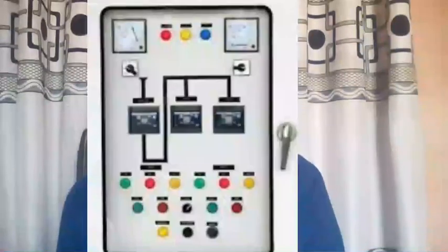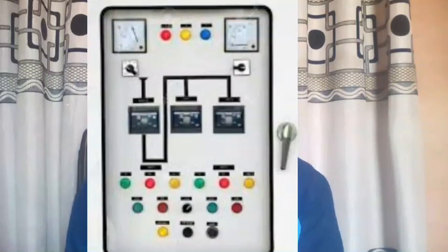And what is it used for? It's used to supply the remote control circuits. We open our breakers remotely, we close them remotely, and it uses the 110 volt. And some relays too use 110-volt supplies for their operation. Likewise, the annunciator alarms in our stations, some of them use the 110-volt battery, 110 volt DC. All is coming from the 110-volt battery bank.